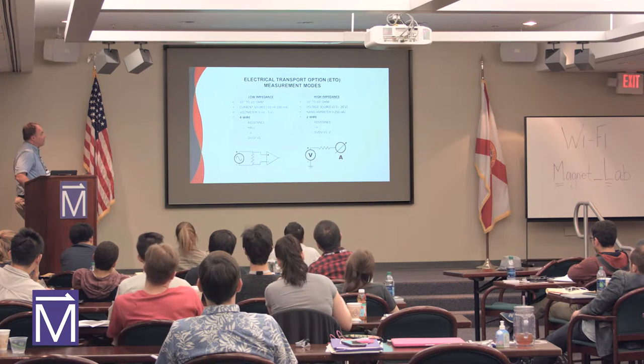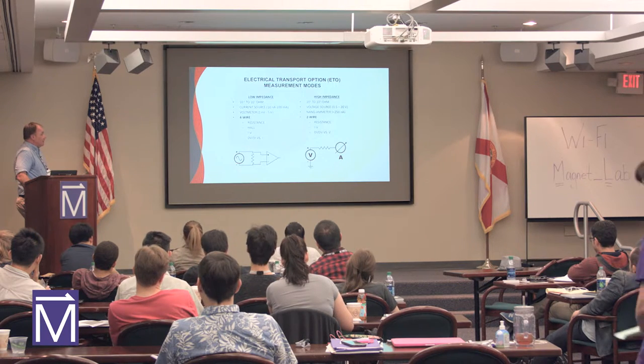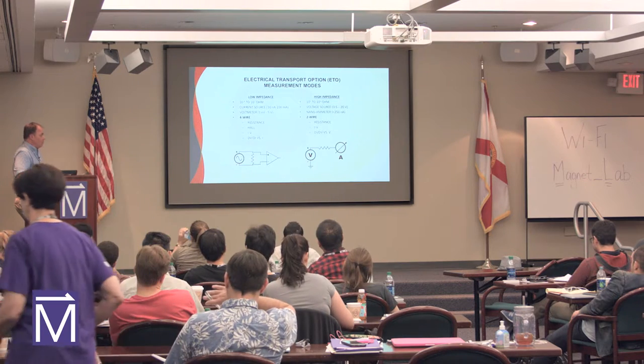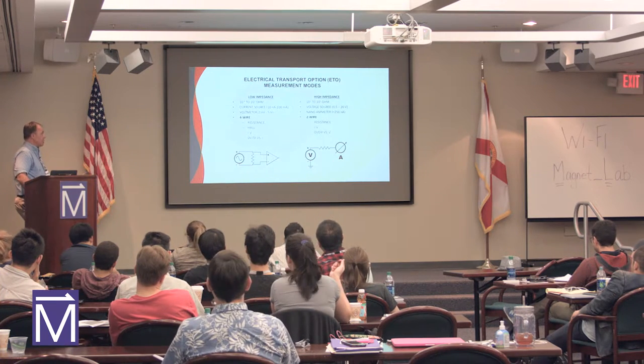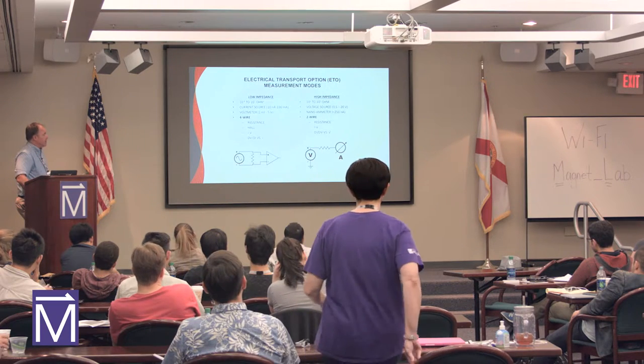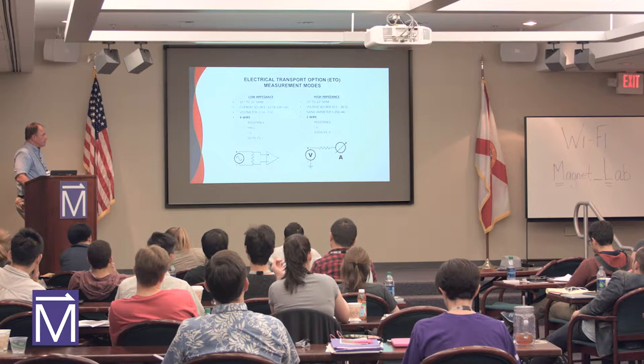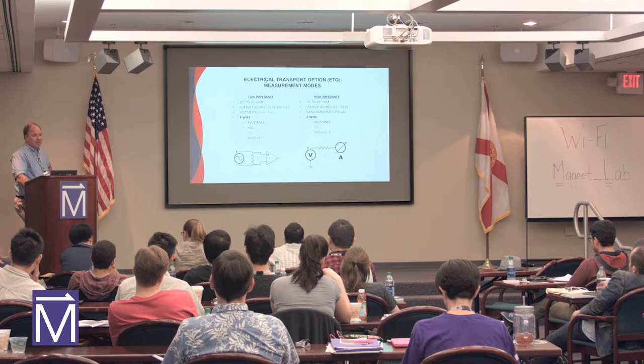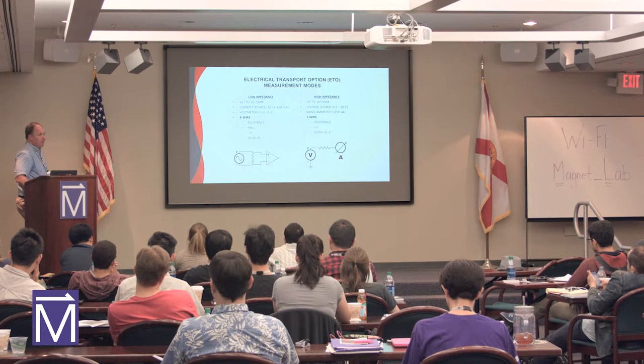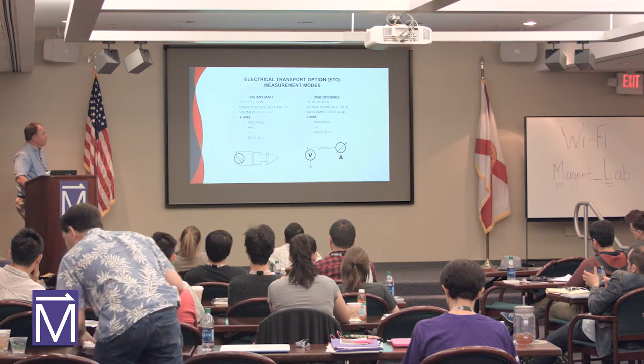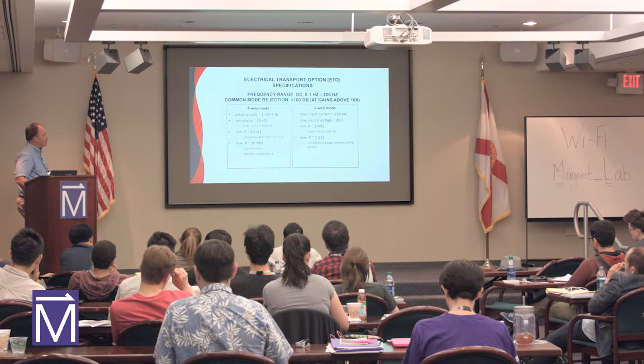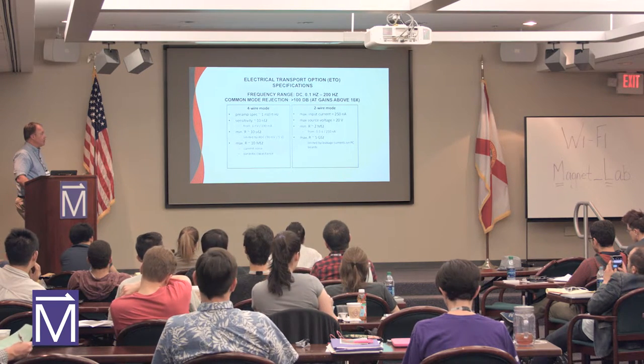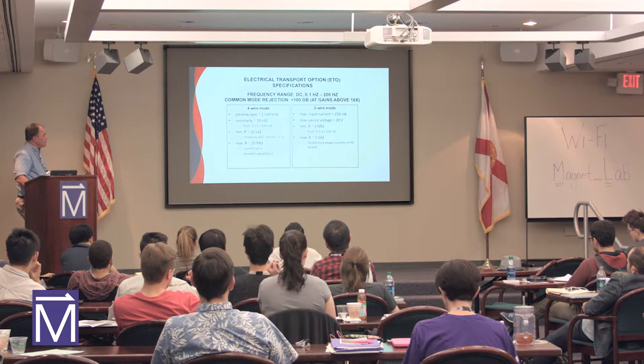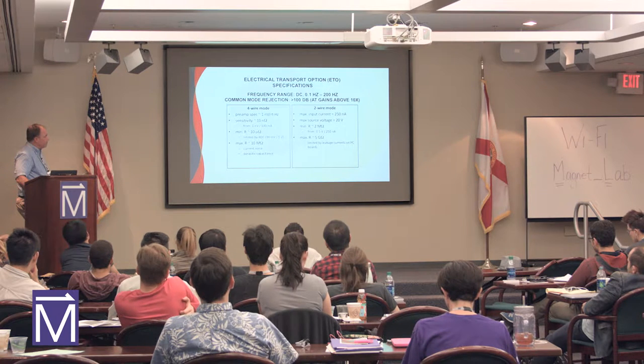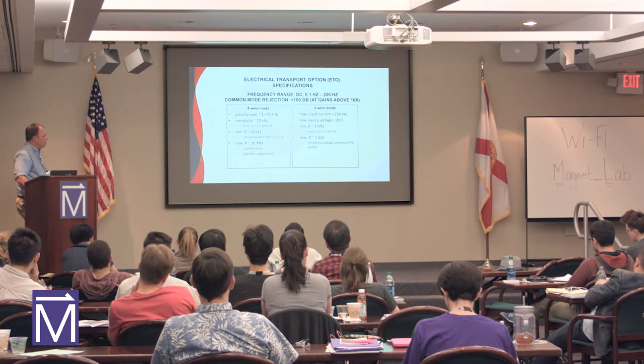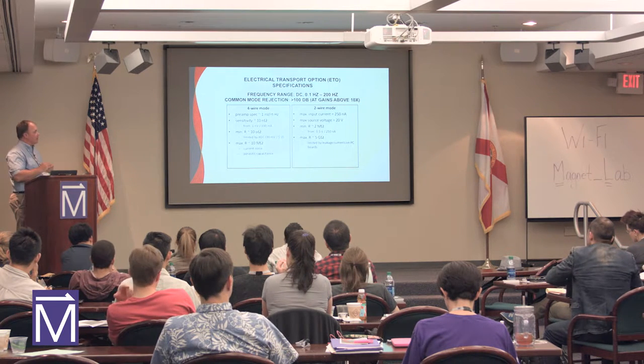So here's a couple of differences. The low impedance technique: 10 nanoamps to 100 milliamps, 1 nanovolt to 5 volt, so the four-wire technique, resistance, Hall effect, IV and differential measurements. And then the high impedance measurement is essentially like the Keithley nanovoltmeter, nanoammeter setup that you might be used to in some of the measurements. Frequency range for the ETO: 1/10 of a hertz to 200 hertz. What's the key thing here? Maximum resistance on the four wire, 10 megaohm, and then 5 gigaohm on the two wire type measurement.